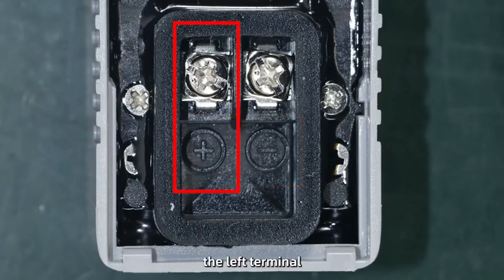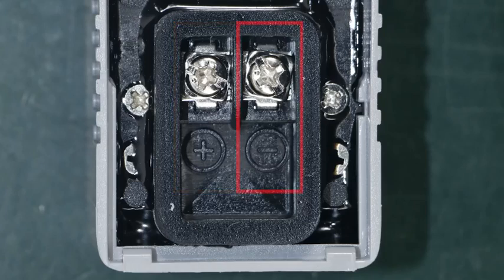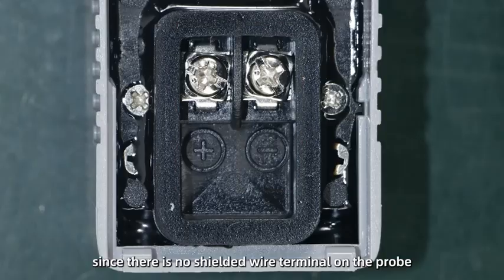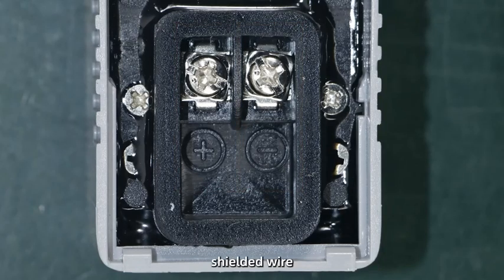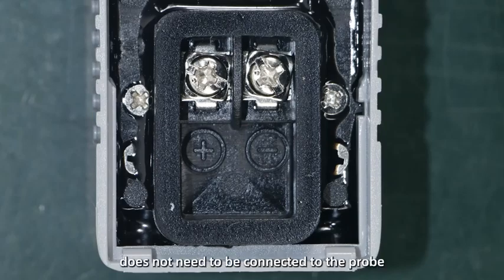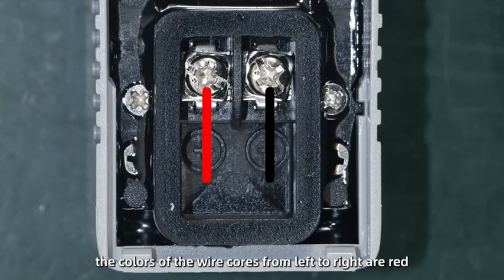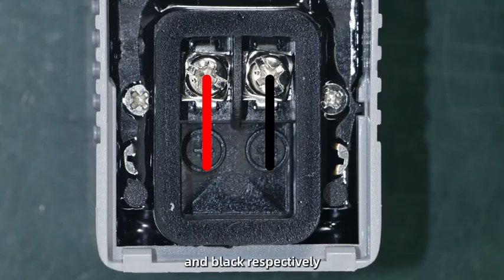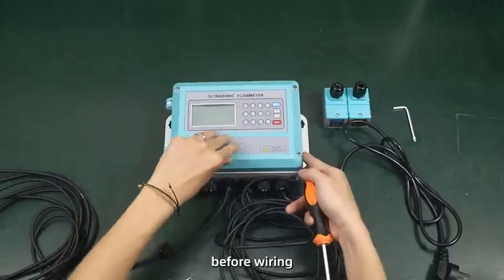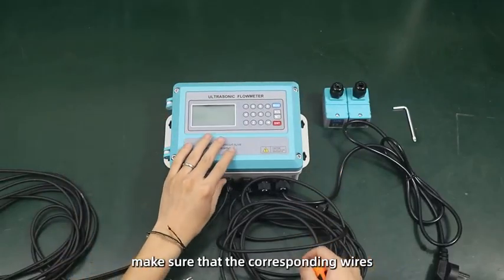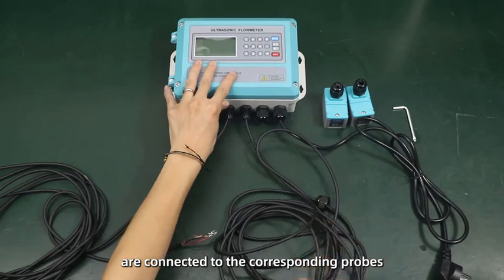The left terminal is connected to the positive electrode, that is, the red line, and the right terminal is connected to the negative electrode, that is, the black line. Since there is no shielded wire terminal on the probe, the copper core shielded wire does not need to be connected to the probe. The colors of the wire cores from left to right are red and black respectively. Before wiring, make sure that the corresponding wires are connected to the corresponding probes.